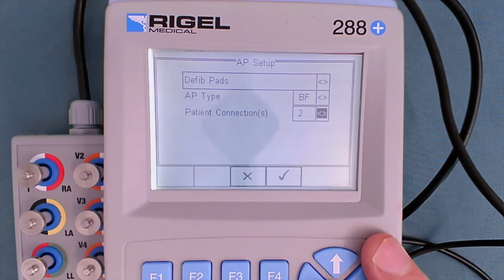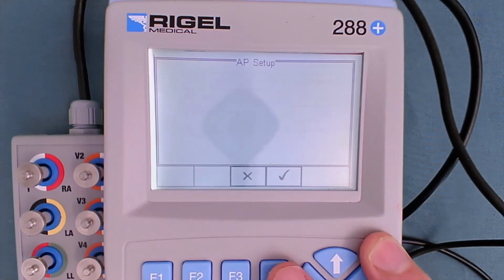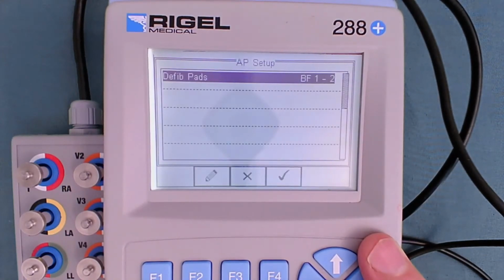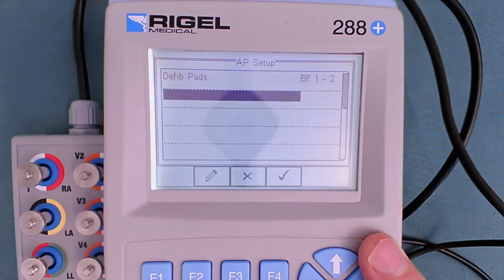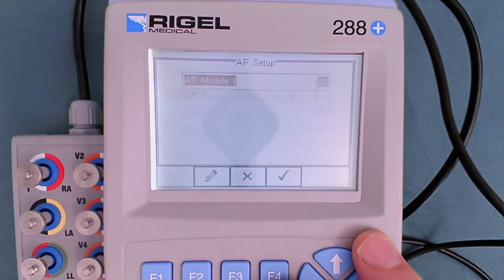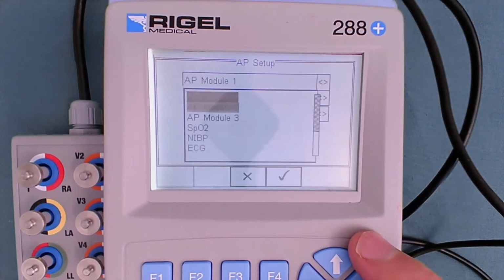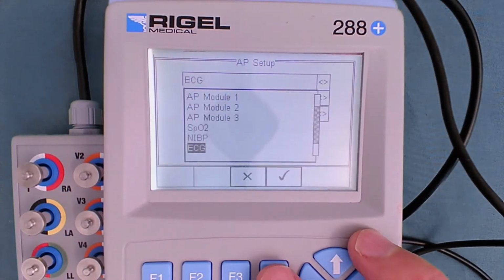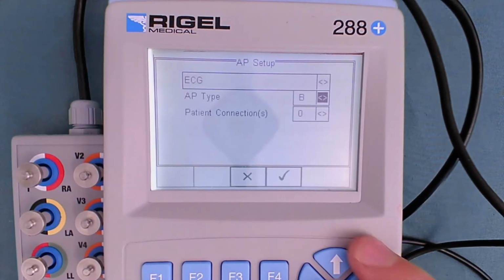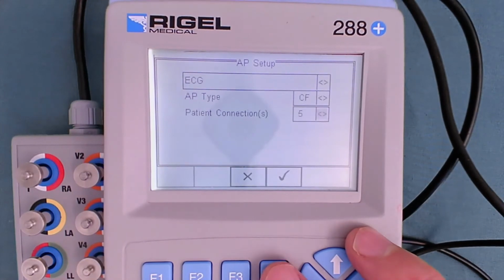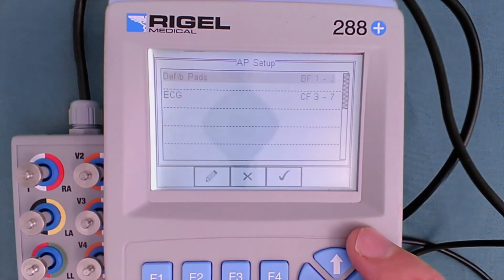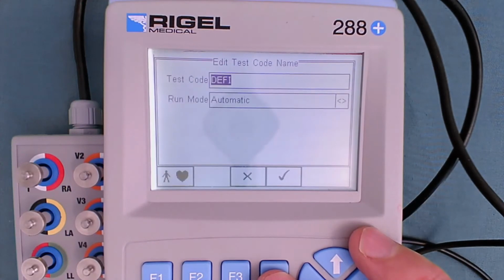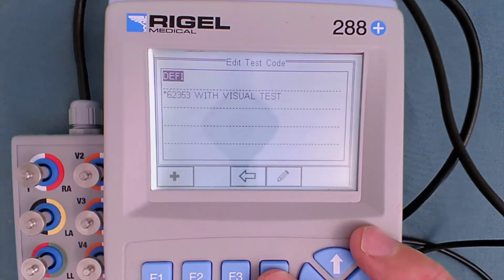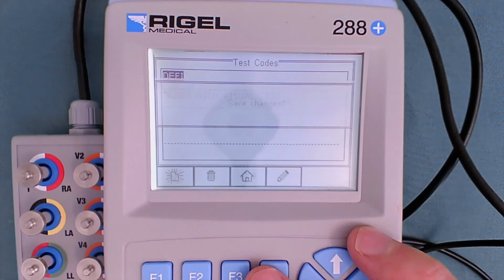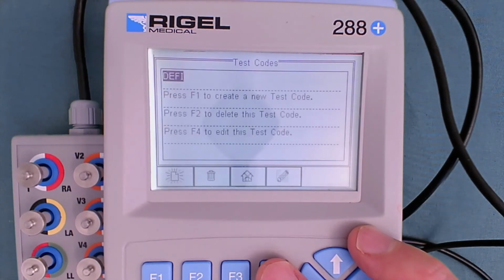And then if we go down using the directional keypad, we can select F2 edit and then add another applied part. For this we'll use ECG. This is CF classification, 5 patient connections. So now we've got a test code that's pre-configured for a defibrillator using our customized test sequence. So if we save that, F3, go back, it's called DEFI. I guess DEFIB would be better, defib, but for demonstration purposes we'll just use that automatic mode.